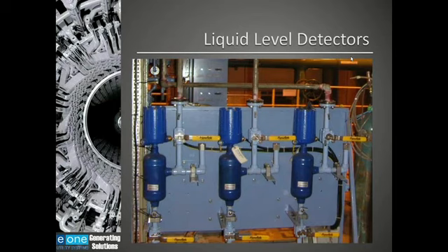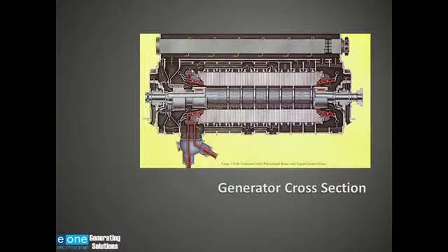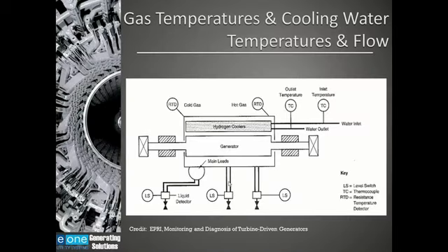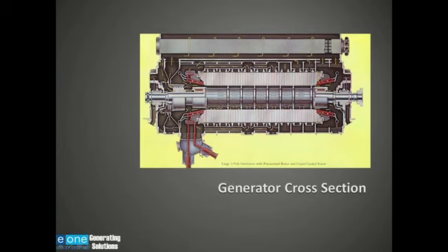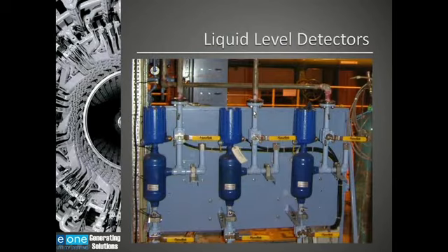These are liquid level detectors, as is indicated here on this drawing. There would be one coming from the bushing box, and then there would be a couple of them coming from the bottom of the case. Two of these are from the case, and one is from the bushing box. This is a reservoir where the liquid will build up. In here is a switch that will switch once you get too much moisture or too much water in these. Note that they've got isolation valves on them so that I can, first of all, drain them, but as importantly, I can shut these down. Over here is a port where I can put liquid into the reservoir to actually test these to make sure that they are working properly.